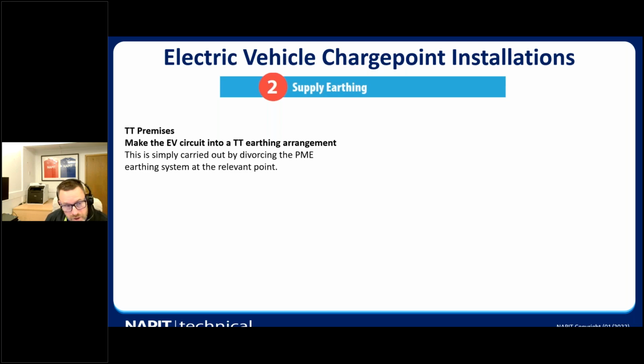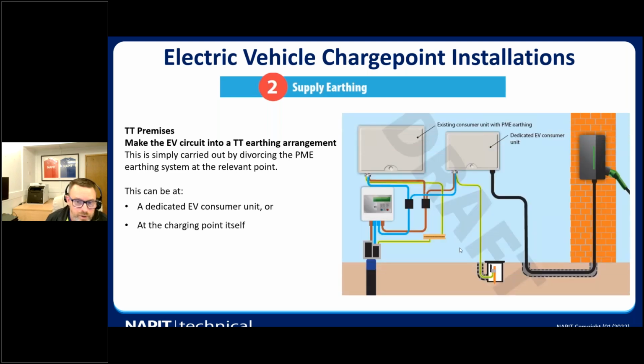Making the EV circuit itself a TT arrangement. This is carried out by divorcing the PME earthing system at the relevant point. This could be a dedicated EV consumer unit or at the charge point itself. And we've got one here where it's a dedicated EV consumer unit for the EV charge point itself, and it's got its own TT system of earthing.